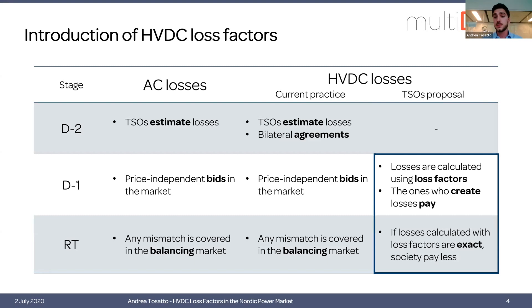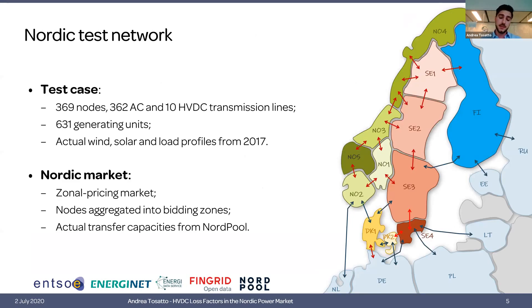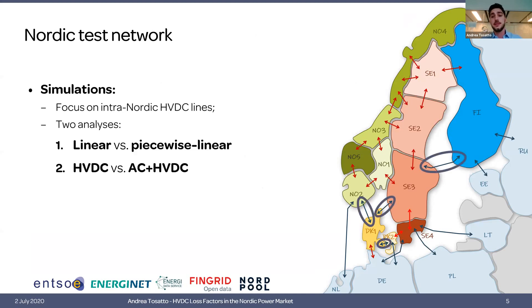The analysis will focus on two aspects. First, are linear loss factors a good representation of the quadratic loss functions? Second, are HVDC loss factors a good enough solution or should we also consider AC losses? To make this analysis we created a test case representing the Nordic system including all generating units from Sweden, Norway, Finland and Denmark, and the actual wind, solar and load profiles. The simulation focuses on four intra-Nordic HVDC lines: Fenno-Skan, Skagerrak, Konti-Skan and Storebælt, with two analyses: linear versus piecewise linear loss factors, and HVDC-only versus AC plus HVDC.